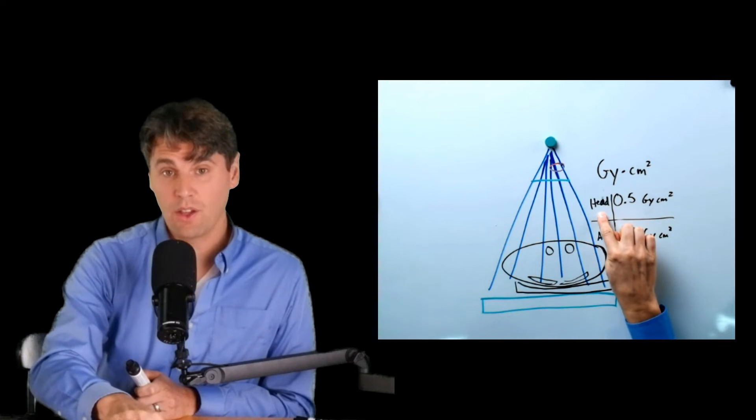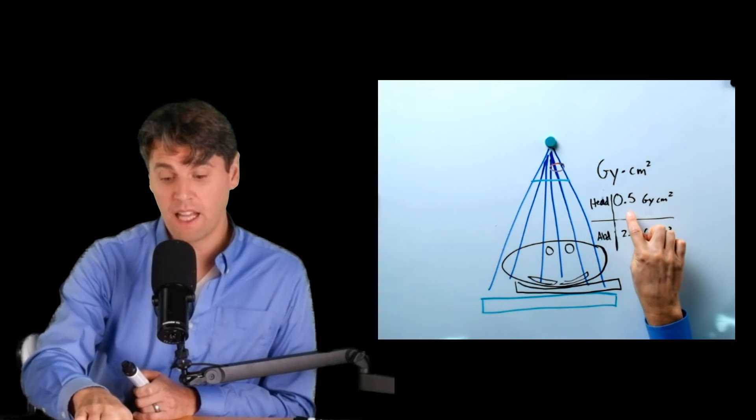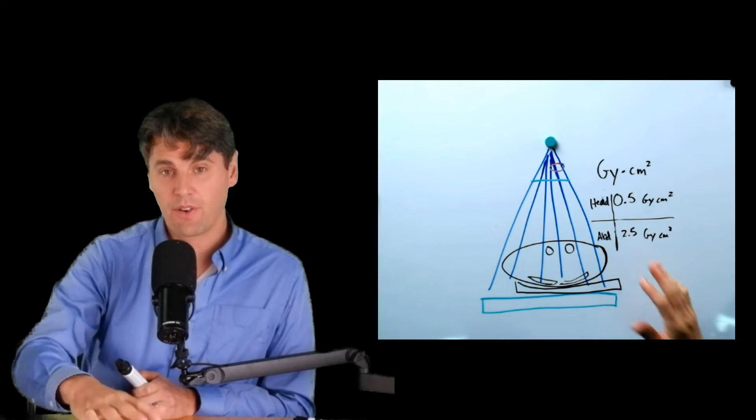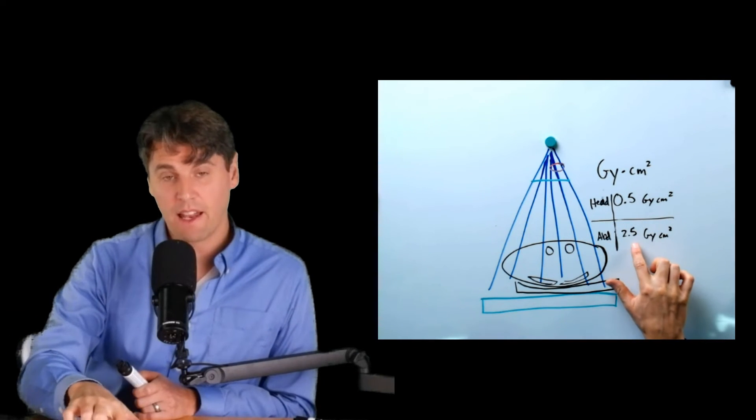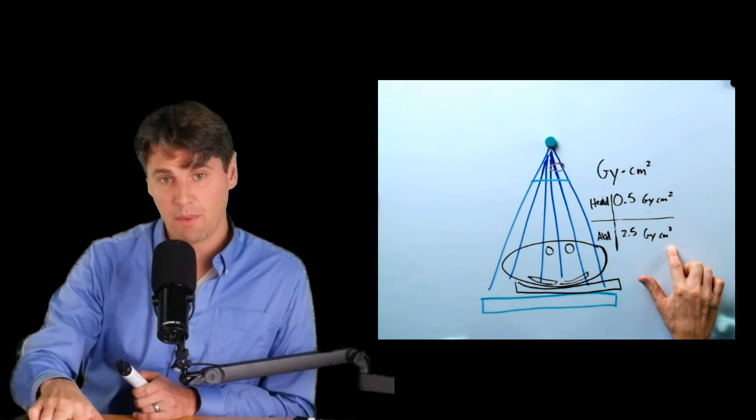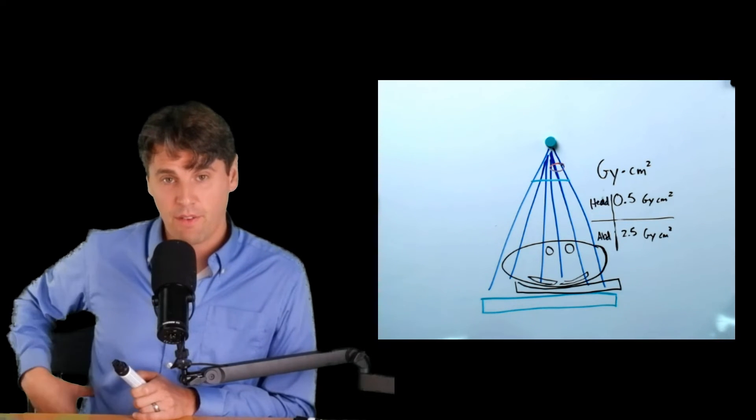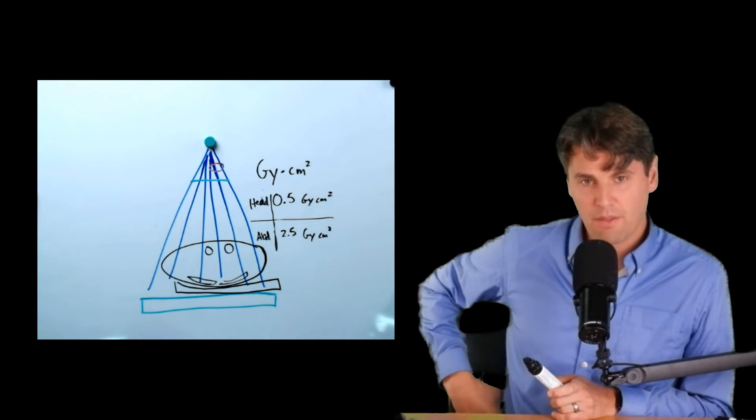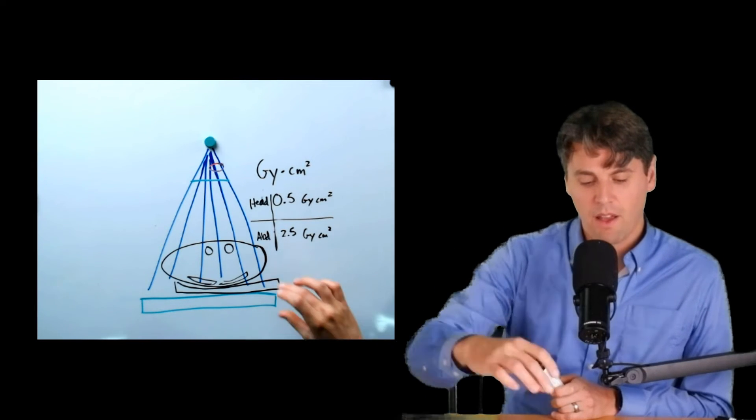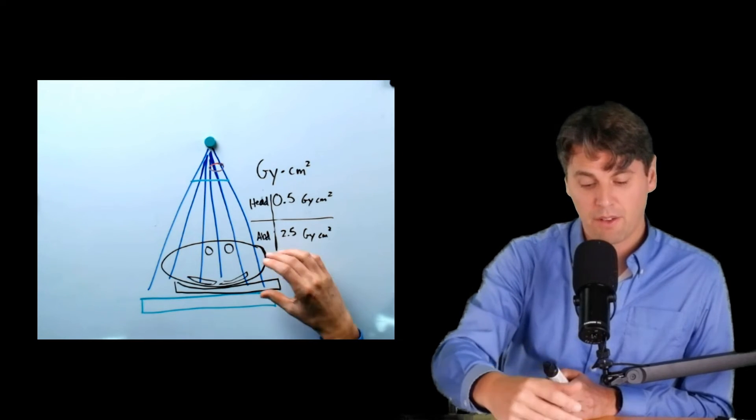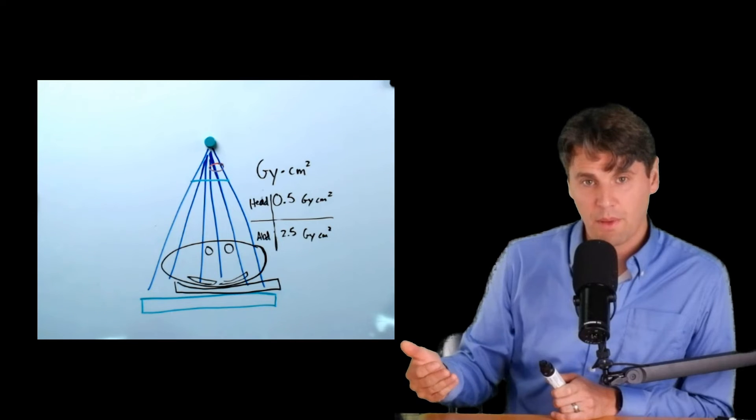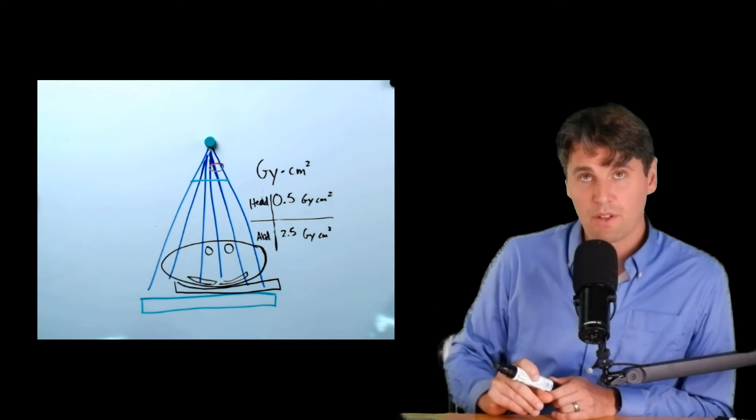For a head, you're usually looking on values around one-half of a gray per centimeter squared for the Kerma area product. And for an abdomen, you're usually looking at about two and a half gray per centimeter squared for a radiograph of the abdomen, for an AP abdomen. These are for adults, and these are just approximate conversion factors, because like we talked about, it's really going to be dependent on a number of factors that you could model.